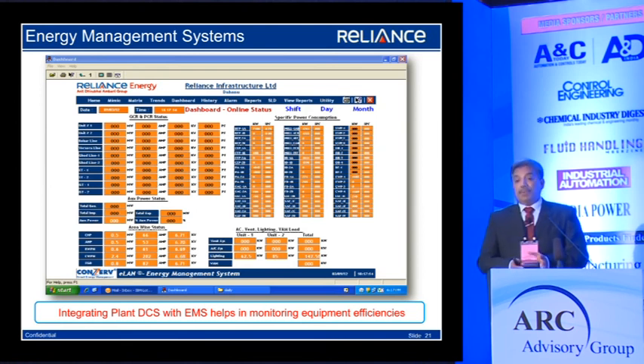For example, with a pump, you calculate the energy required to pump a certain amount of water. You see what the flow is, what the pressure is, that's the specific output, and you calculate the specific input. You divide them to get a signal of the equipment's efficiency. We've implemented this across all auxiliaries in the power plant.